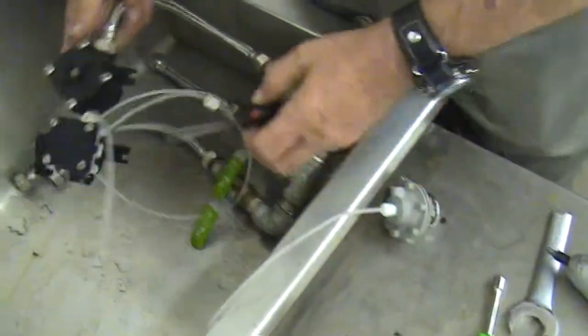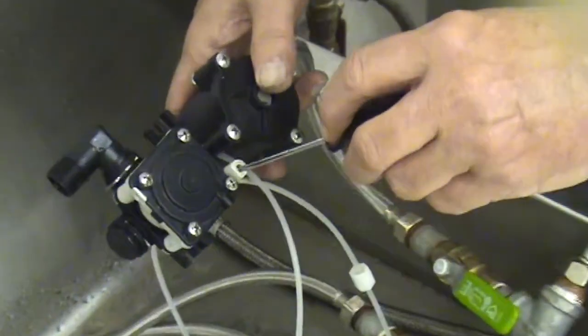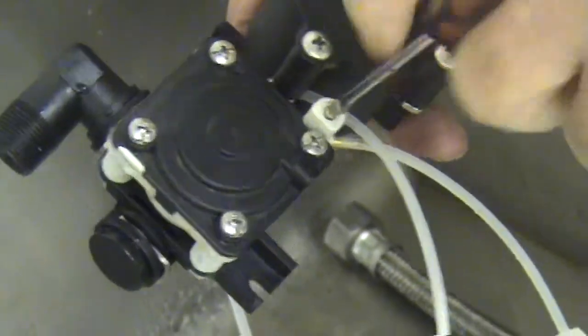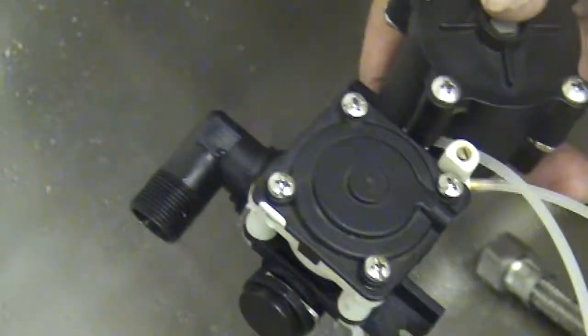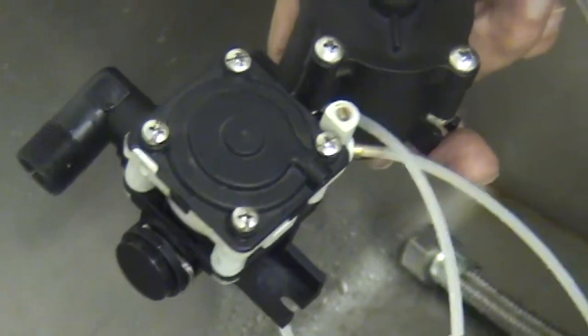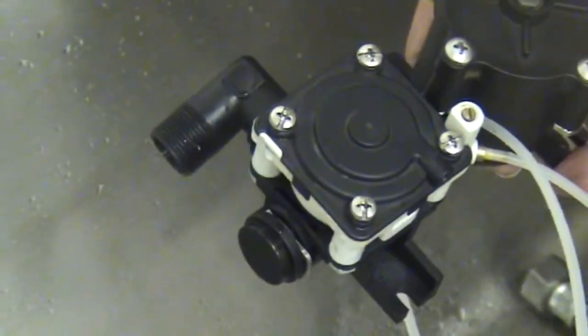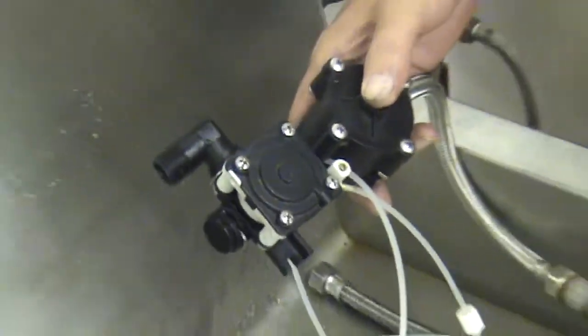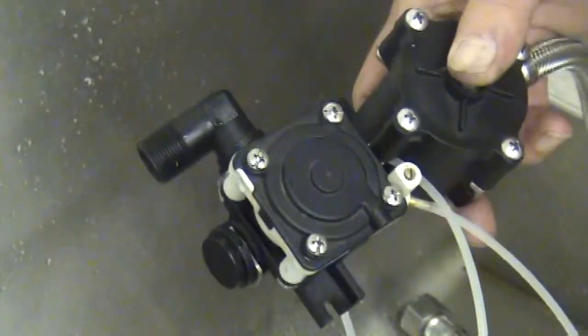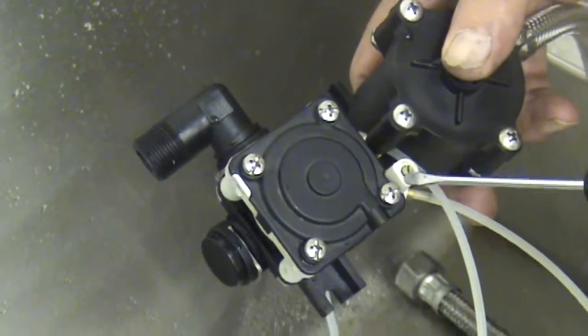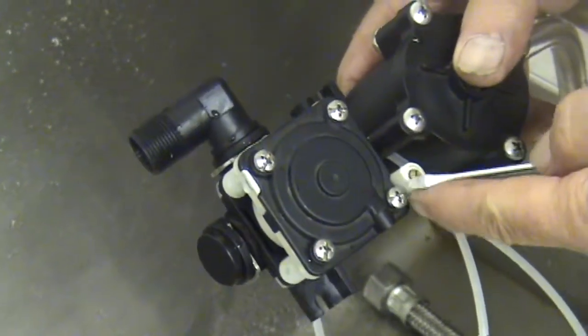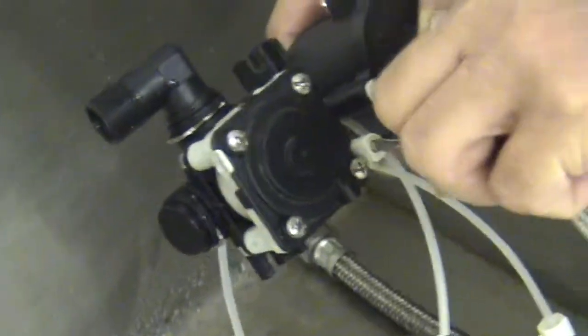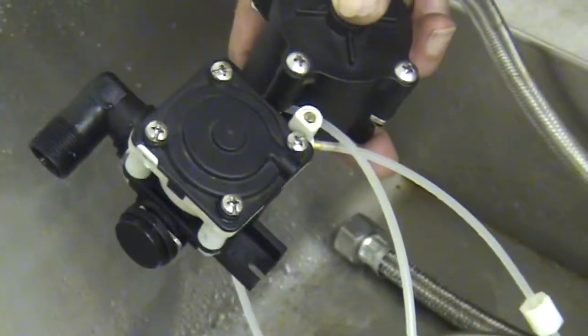In some cases, you can have a valve that's working perfectly, but if someone has taken the adjustment on the cycle all the way out, you can push the button and it will not come on. You notice there, if we push the button twice in succession, we get a little bit of spray, but the air or the vacuum we're creating is escaping through the timing adjustment. So we want to take that adjustment and screw it in probably a couple of turns and try the button again.